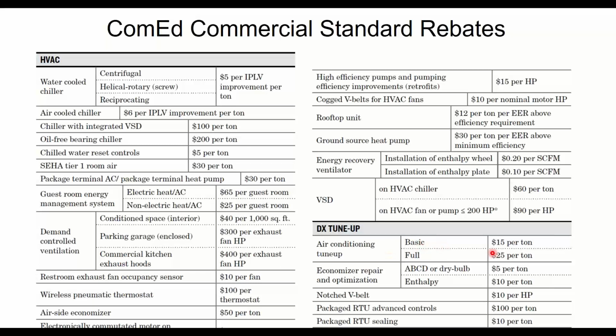There are descriptions of what's required, but essentially a basic tune-up is cleaning the condenser and evaporator coil, along with some measurements. A full tune-up is the same as the basic, plus, because of the measurements you made, you realize you needed to adjust the refrigerant charge, and they give you more money for that.